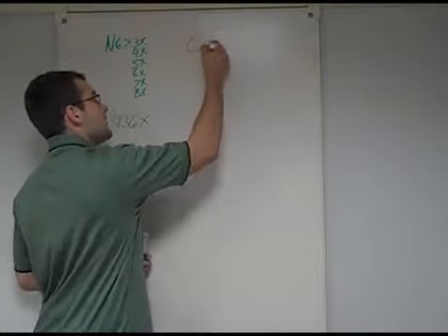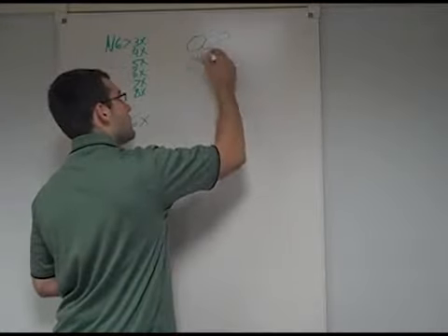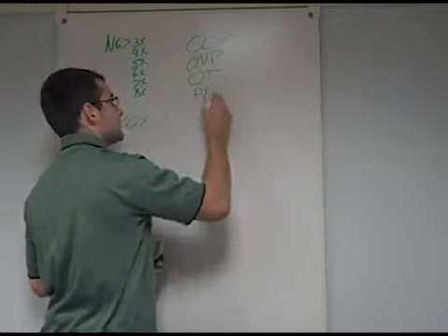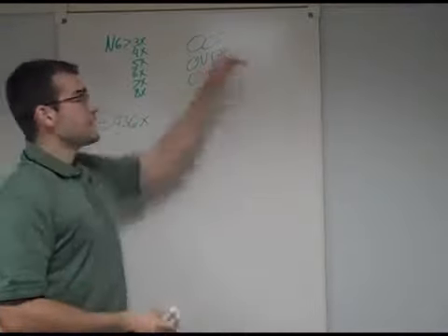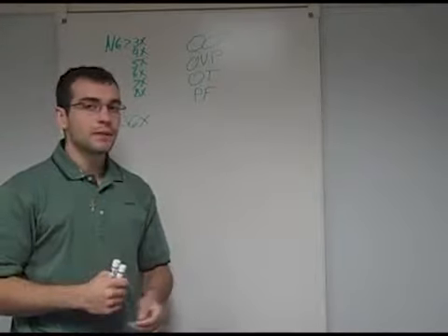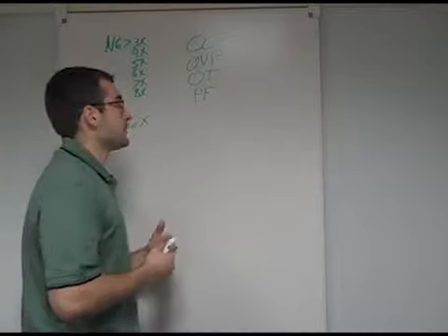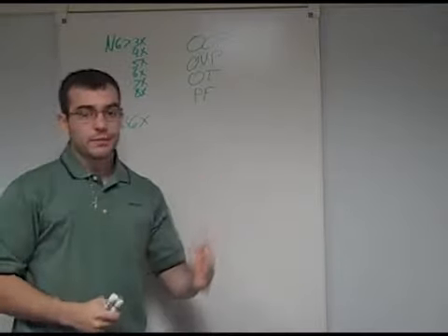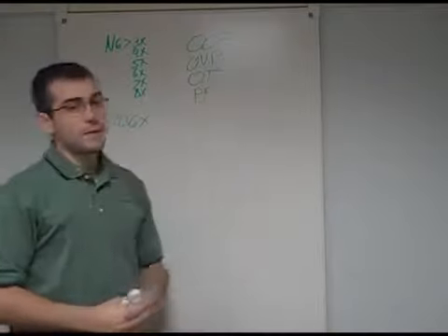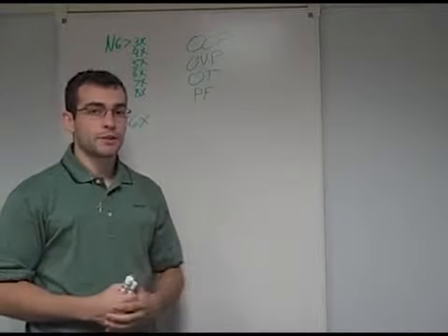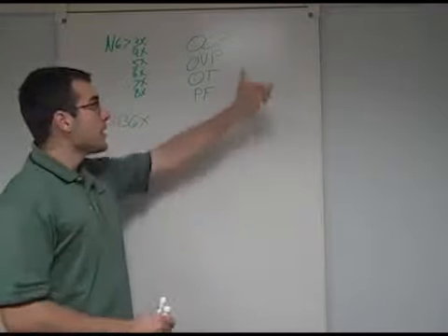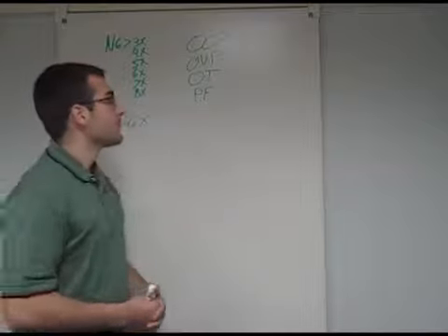These are the OCP, OVP, OT, and PF. Now the OCP is the overcurrent protection. This is a programmable value, but it needs to be enabled for it to be active. So once the current reaches this limit, the power supply's outputs will be turned off. Likewise, the OVP is the overvoltage protection, and once the voltage reaches its limit, the outputs will be turned off. However, the OVP is always enabled.